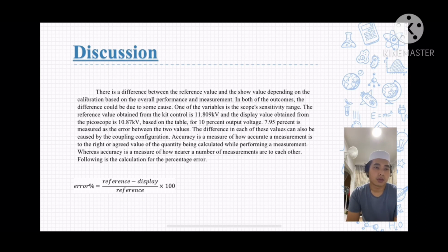The difference in each of these values can also be caused by the coupling configuration. Accuracy is a measure of how close a measurement is to the right or true value of the quantity being measured, whereas precision is a measure of how near a number of measurements are to each other. Following is the calculation for the percentage error. This is the formula for the percentage error: reference minus display, divided by reference, and multiplied by 100%.